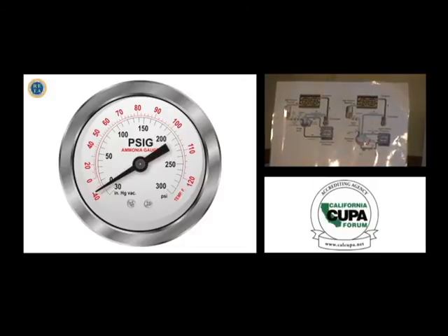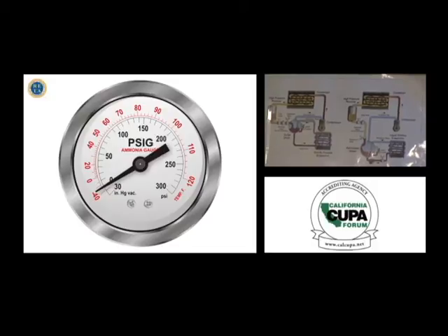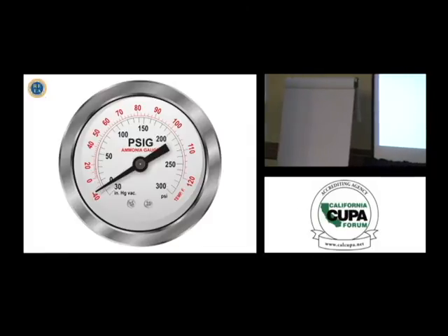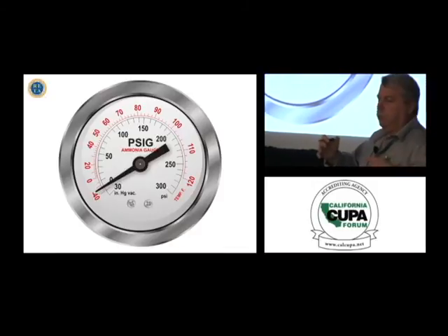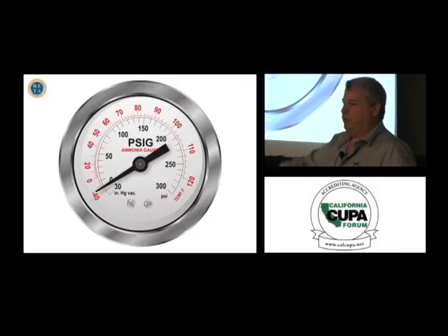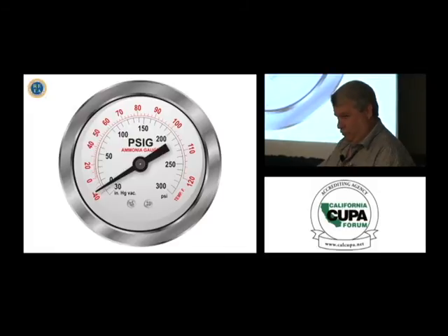For example, at the outlet of the pump that goes out to the units, the pressure could be, grab a number, 30 psig, but my system is operating at 15 psig as far as compression. The fluid has the mechanical energy of the work of the pump. That is called subcooled, because our pressure and our vapor pressure are not in agreement. Those are all part of the nuances of industrial refrigeration that we work with in order to get the job done. So, long story short, for refrigeration, the fluid is ready to change state, and the direction of heat energy coming in will be saturated to make gas, and heat energy going out will take from the gas and back into a liquid.